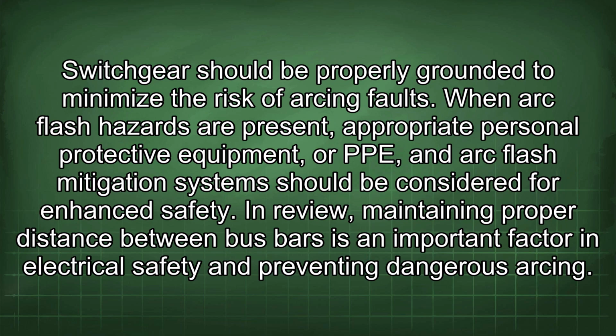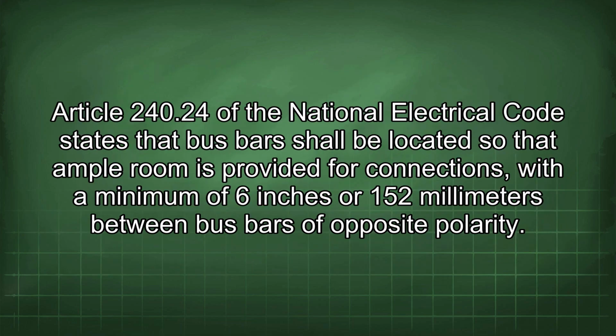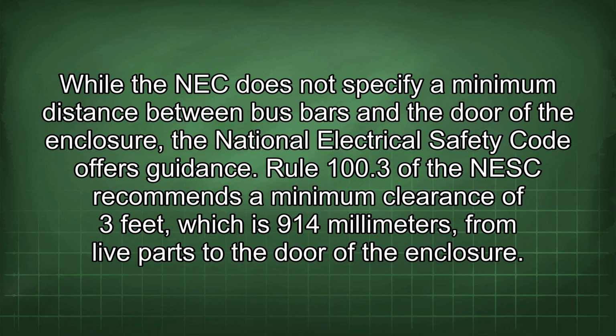dangerous arcing. Article 240.24 of the National Electrical Code states that bus bars shall be located so that ample room is provided for connections, with a minimum of 6 inches or 152 millimeters between bus bars of opposite polarity. While the NEC does not specify a minimum distance between bus bars and the door of the enclosure, the National Electrical Safety Code offers guidance.